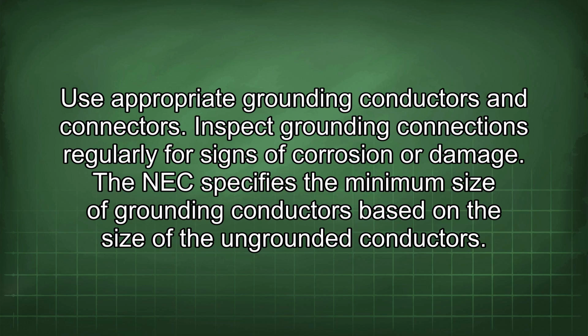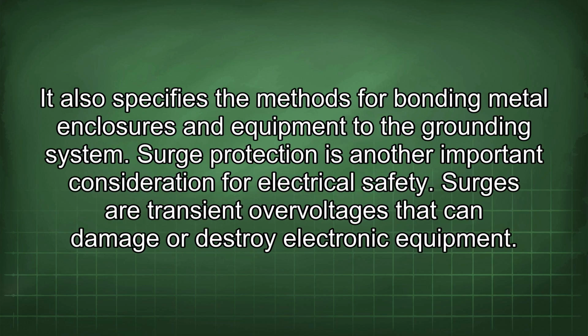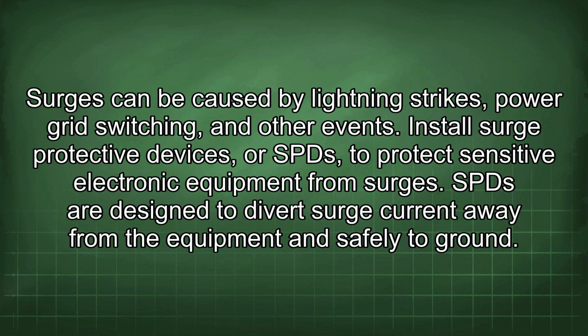The NEC specifies the minimum size of grounding conductors based on the size of the ungrounded conductors. It also specifies the methods for bonding metal enclosures and equipment to the grounding system. Surge protection is another important consideration for electrical safety. Surges are transient overvoltages that can damage or destroy electronic equipment. Surges can be caused by lightning strikes, power grid switching, and other events.